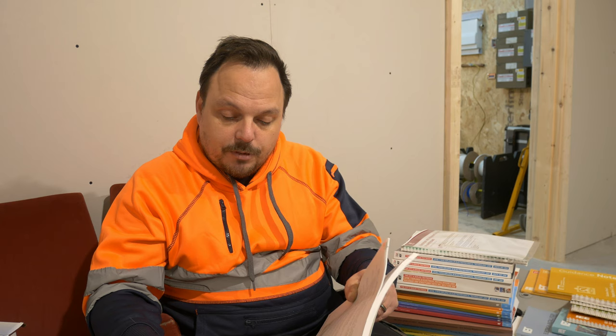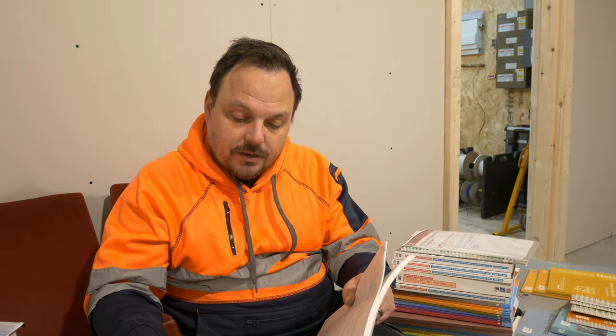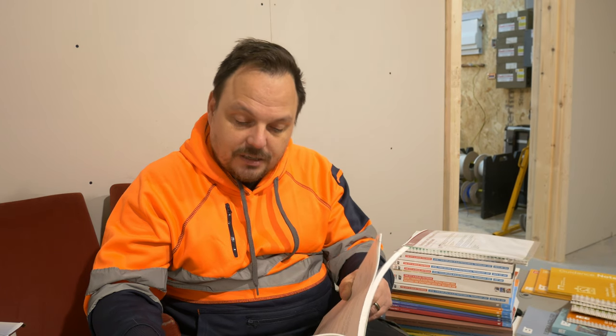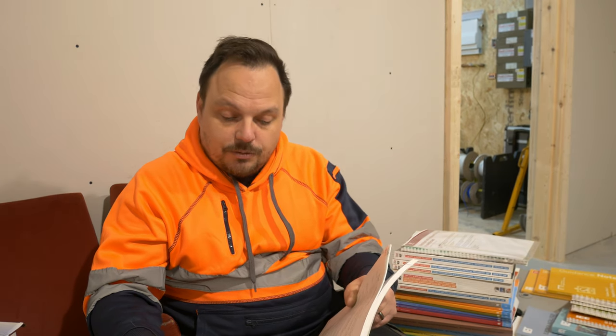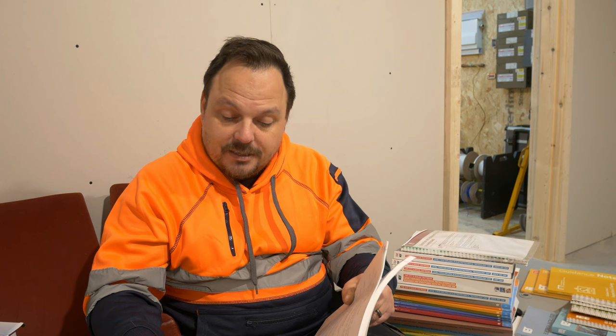And a cable complying with an appropriate standard having a non-metallic sheath or a non-metallic enclosure is deemed to provide satisfactory basic protection and fault protection, as does an item of Class 2 equipment. Hence the metal cable tray or basket need not be earthed.